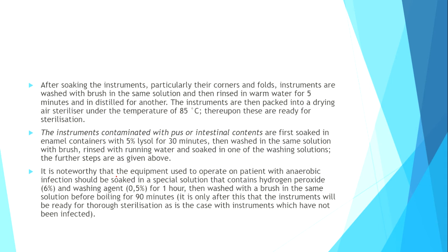After soaking the instruments, particularly their corners and folds, the instruments are washed with a brush in the same solution and then rinsed in warm water for 5 minutes and then in distilled water for another 5 minutes. The instruments are then packed into a drying air sterilizer at a temperature of 85 degrees Celsius. Thereupon, they are ready for sterilization.